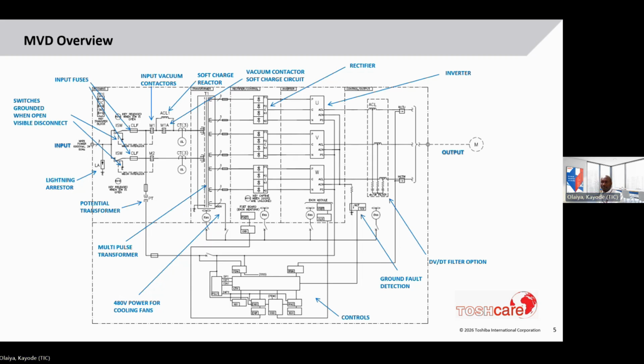Then we have input fuses, which are for short circuit protection, followed by potential transformers, which supply voltage to the controls. Then we see the input contactor, which provides power to the rest of the drive, followed by a pre-charge circuit consisting of a soft charge reactor and a contactor, which bypasses that reactor when the DC bus voltage gets to a certain level. The purpose of that soft charge reactor is to limit the inrush from the transformer.